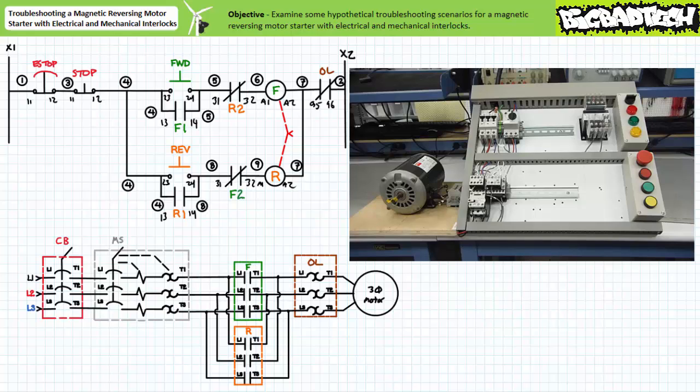Recall our magnetic reversing motor starter with electrical and mechanical interlocks exhibits the following behavior. When an operator presses and releases the forward push button, the left contactor physically closes and the motor rotates in one direction. While in forward mode, the closure of the reverse push button serves no purpose since the electrical interlock provided by the contact F2 does not allow the reversing contactor coil to be energized.